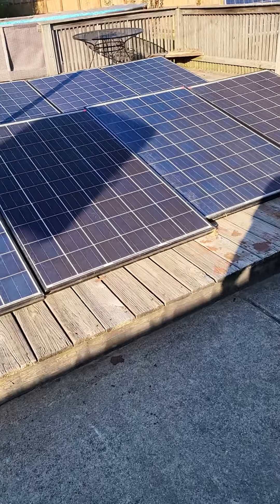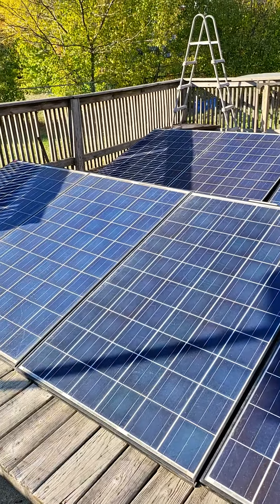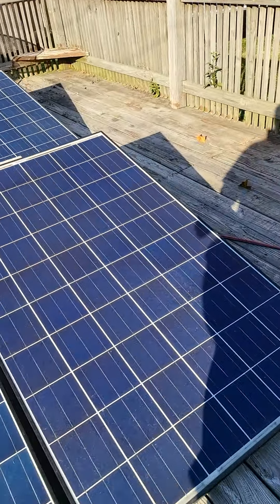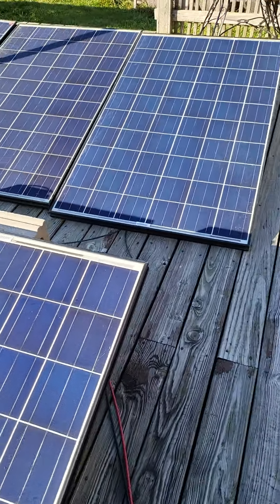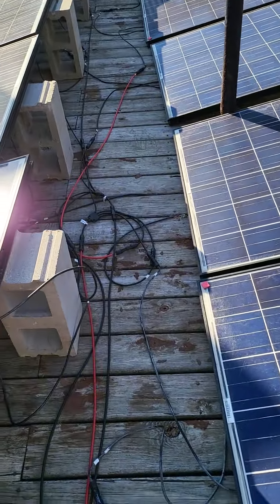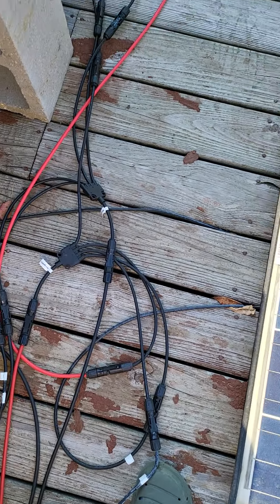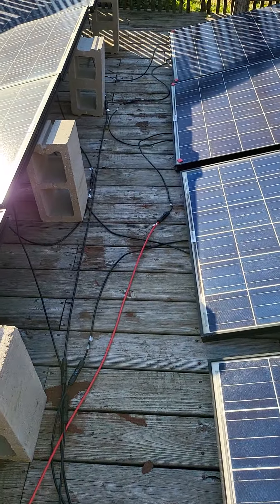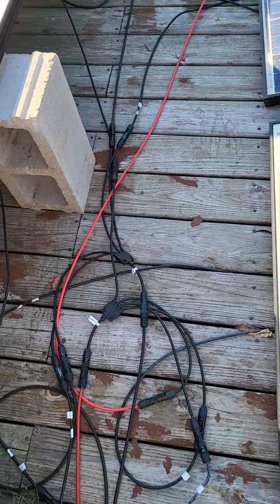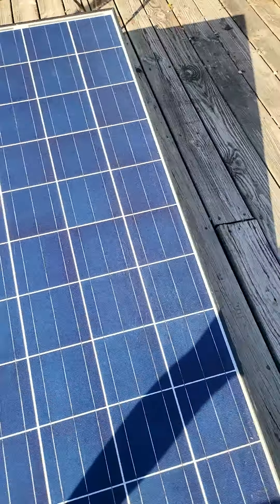I was asked how my array was looking. This is 3000 watts. I have them wired in series and then in parallel — four parallel strings with three panels wired in series each, so that's 750 times four. Do the math and basically that's where we're at.